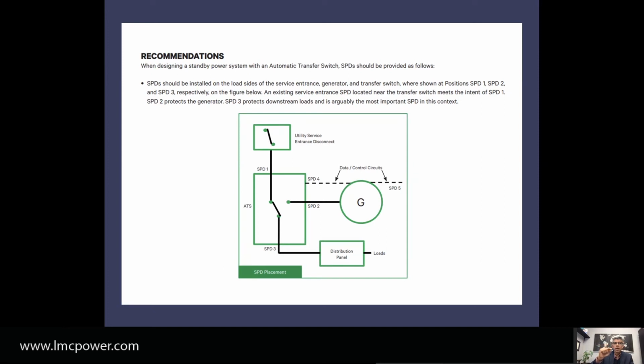You also want an SPD3 on the bottom panel—that's your category B. When the generator kicks in, it generates a transient too, and you want to protect against that before it reaches the rest of the equipment connected to the next panel. So you have category C at the input of the ATS, and category B at the output of the ATS. That's how they recommend it.